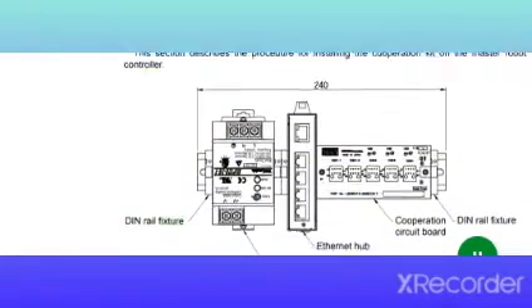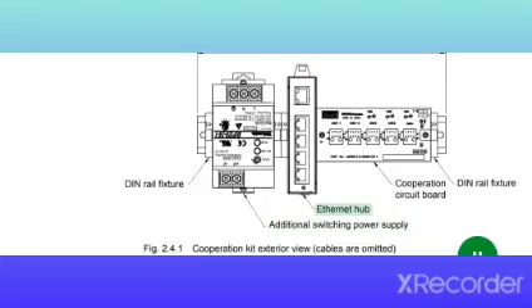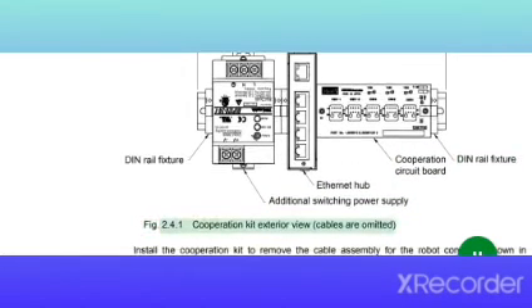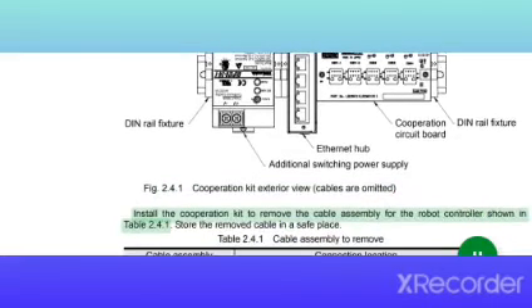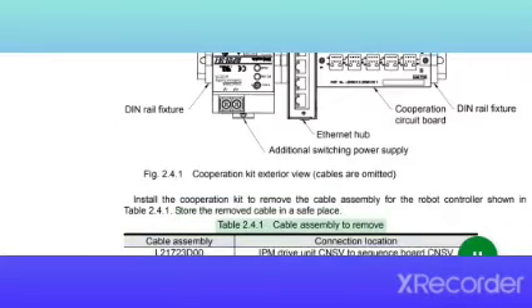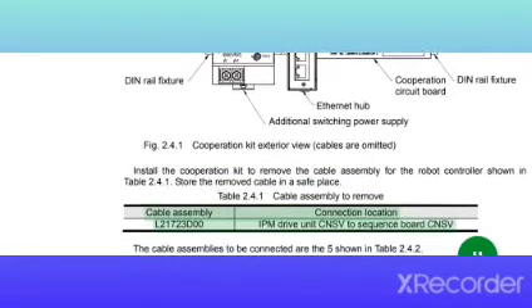DIN rail fixture. Additional switching power supply. Ethernet hub. Cooperation circuit board. DIN rail fixture. Fig. 2.4.1 Cooperation kit exterior view, cables are omitted. Install the cooperation kit and remove the cable assembly for the robot controller shown in Table 2.4.1. Store the removed cable in a safe place. Table 2.4.1 Cable assembly to remove. Cable assembly, connection location: L21723D00, IPM drive unit CNSV to sequence board CNSV.